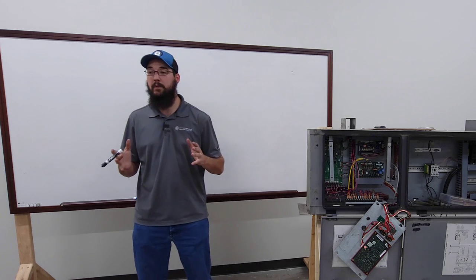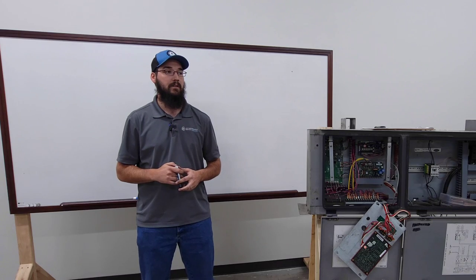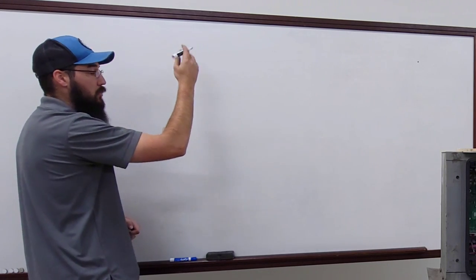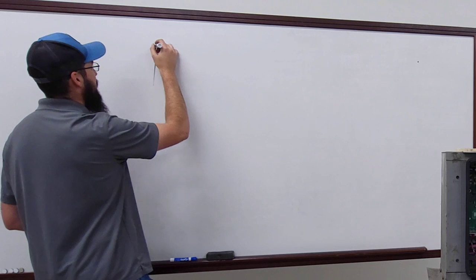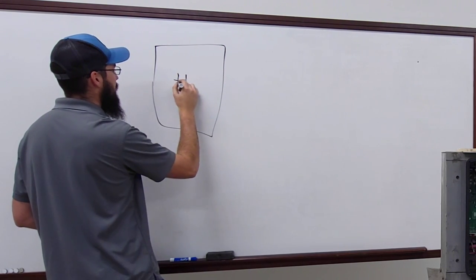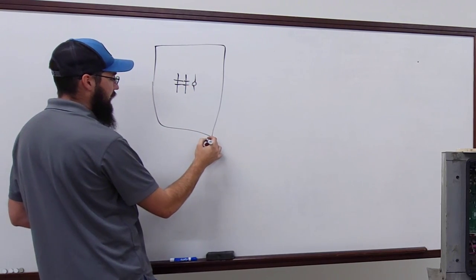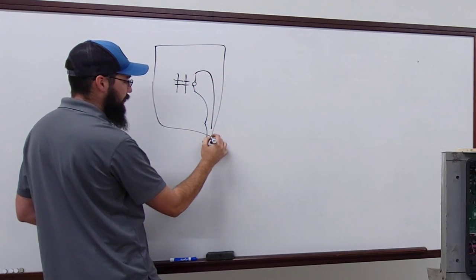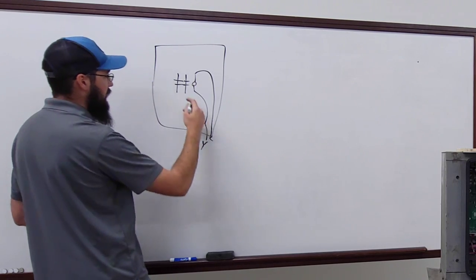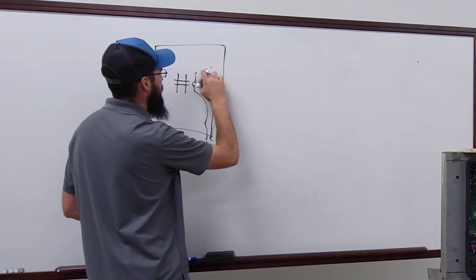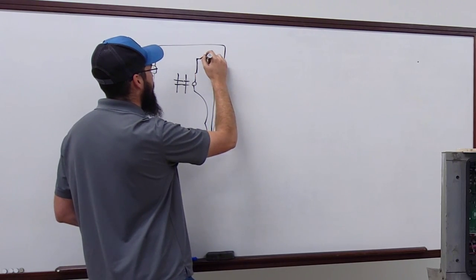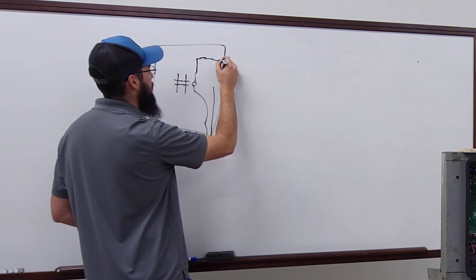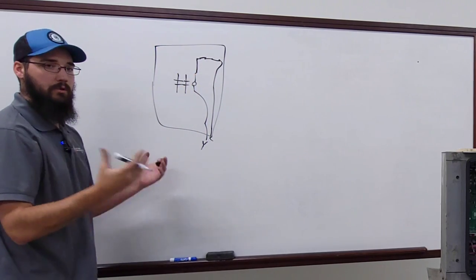It used to be as simple as walking up to a split system panel with just a contactor — you had a coil, a Y wire would come in, land, and come right back out to the common. That was it. It turned the contactor on. Then it got a little more advanced: you started tying in a high pressure switch — technically normally closed — and then a low pressure switch. Either of those trip, the unit shuts down. That was it.